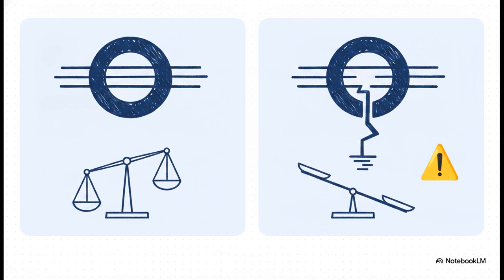Method 1 relies on the toroidal, or ring, current transformer. The CTs are physically wrapped right around all three phases of a feeder cable. Under perfectly healthy, normal conditions, the vector sum of the three phases, L1 plus L2 plus L3, equals exactly 0. The currents balance out perfectly within the ring. But if an earth fault hits, that balance is instantly broken. Current is leaking to earth, so it's not returning through the phase conductors. Suddenly, that residual sum doesn't equal 0 anymore. It directly equals the earth fault current itself, which we call IE. The toroidal CT sees this imbalance the millisecond it happens.